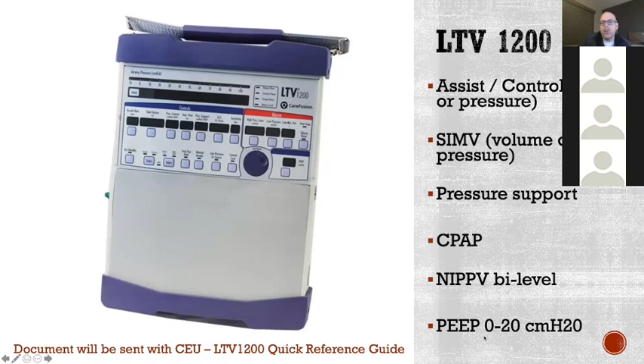What it would look like on the user screen looks a little more complicated to set up, but it's actually pretty straightforward and easy. It turns on with the power button down here. And then for all the settings, we just press the button, turn the dial, and then press the button again to confirm it. So if I wanted 12 breaths a minute, I would press breath rate, turn it to 12, press breath rate again. Click on tidal volume, turn it to the tidal volume I want, click it again. All the buttons work just like that on this ventilator.